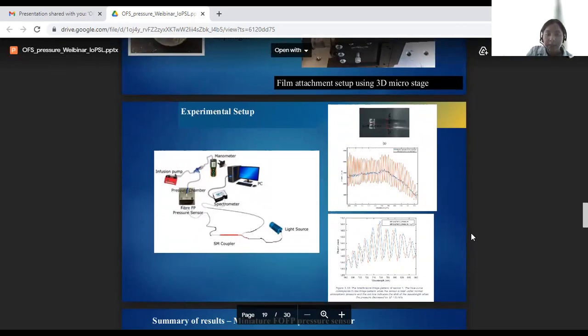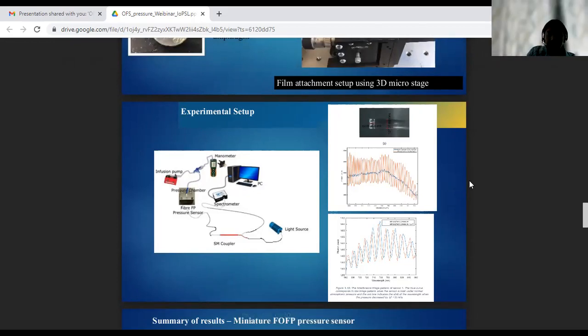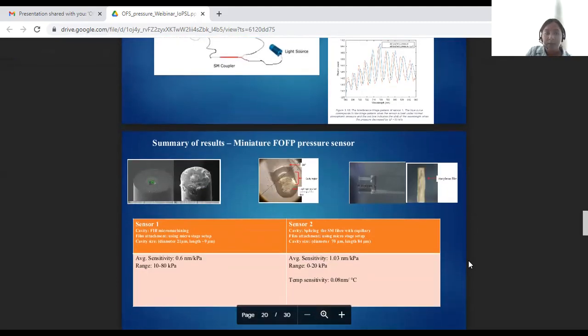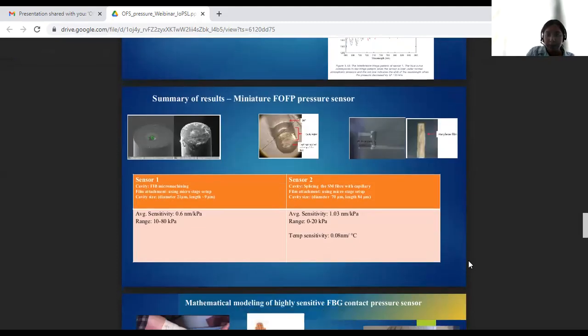This one shows the experimental setup that has been used to calibrate the sensor. We have a commercially available manometer, which was used to calibrate the sensor, and the fiber was enclosed in a pressure chamber and infused with air using an infuser. Simultaneously, the interference fringe pattern was obtained and logged along with the pressure changes. The figure in the top right, blue line, corresponds to the reflection spectrum without application of any film to the tip of the cavity. And the orange one shows how the interference fringe pattern looks after the application of the diaphragm. And the bottom right picture shows how the interference fringe pattern shifts with the pressure. Next slide, please. And this shows the two sensors that have been made with their sensitivities. Can I have the next one, please?